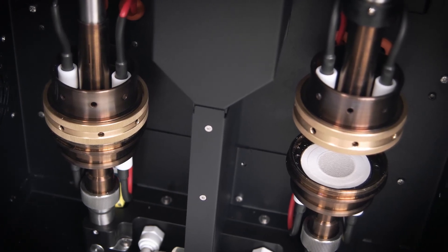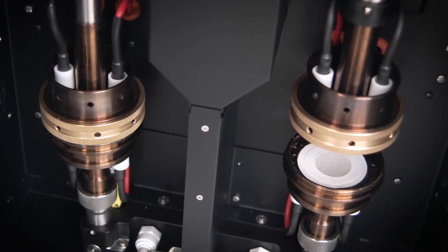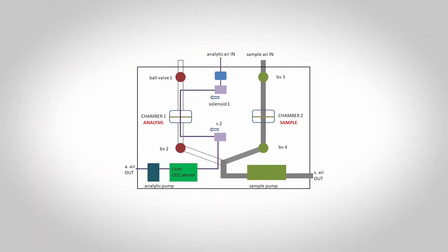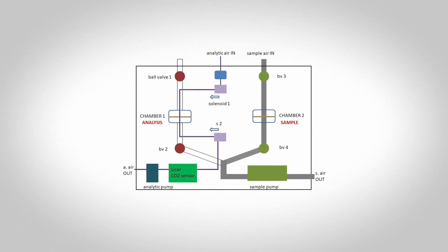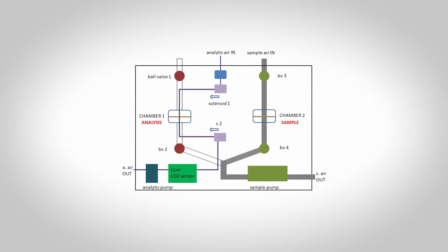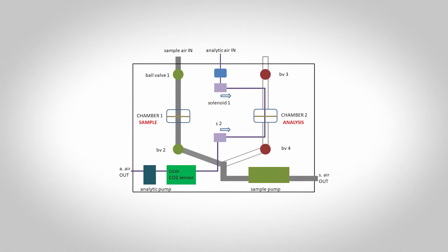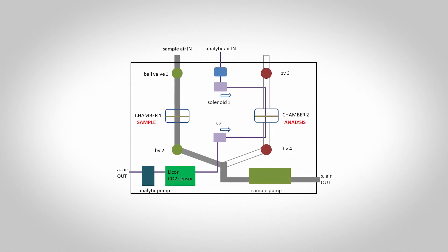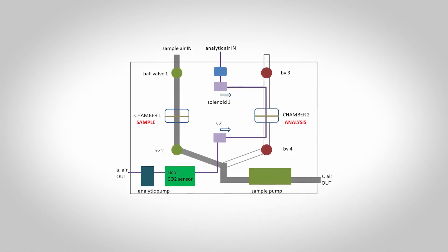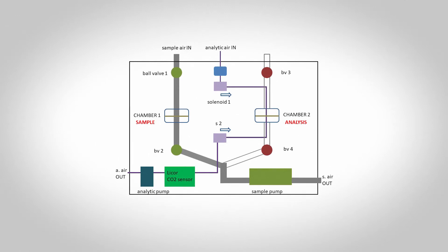The sample stream flows to a quartz fiber filter and makes an aerosol deposit very close to the flash heating elements. When the collection period ends, the valves switch air from sampling to analytical air. The flash heating elements are switched on and all the carbon is converted to CO2, making a large pulse of CO2 in the detector.